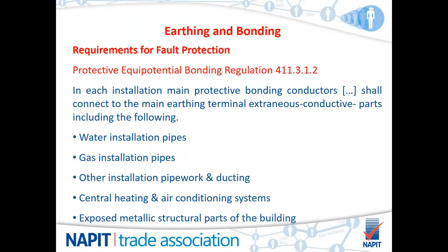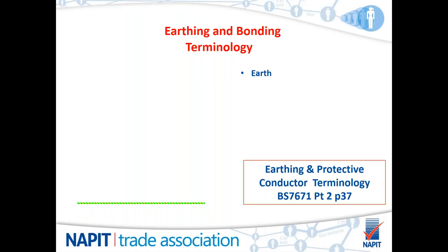So, Protective Equipotential Bonding Regulation 411.3.1.2. In each installation, main protective bonding conductors shall connect to the main earthing terminal extraneous conductive parts, including the following: water installation pipes, gas installation pipes, other installation pipework and ducting, central heating and air conditioning systems, and exposed metallic structural parts of the building.